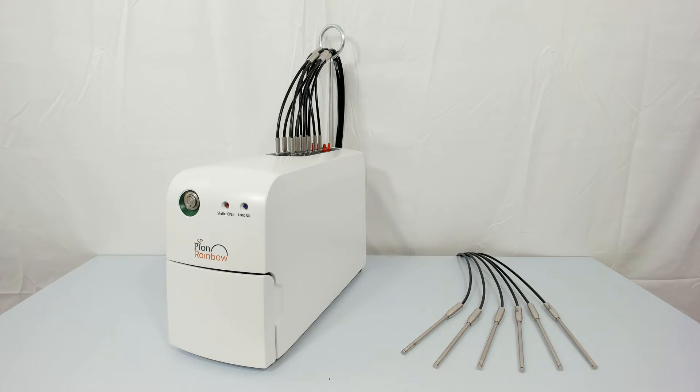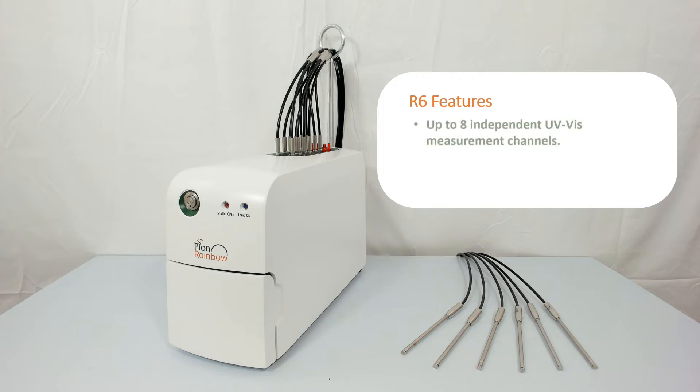The R6 can be fitted with up to a maximum of eight parallel UV-Vis measurement channels, seen here along the top of the instrument. Each features an independent UV-Vis spectrometer and fiber optic dip probe, allowing for the acquisition and real-time processing of concentration data at a freely variable collection interval for up to eight assay vessels in a single run.